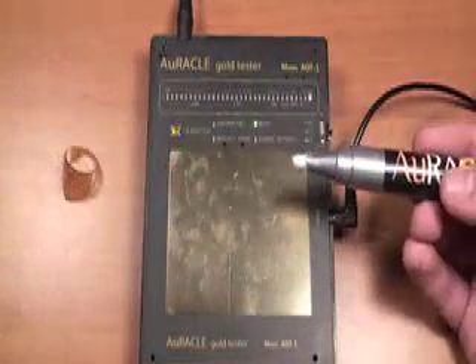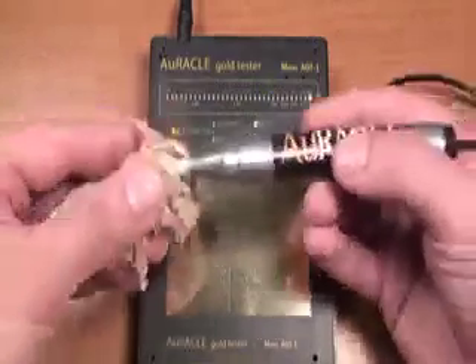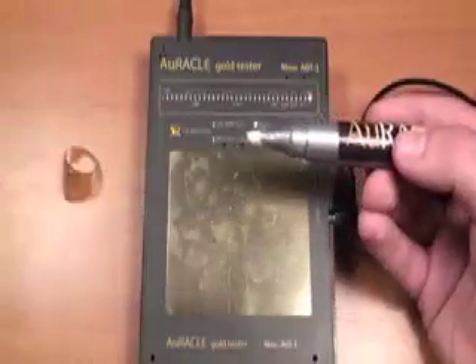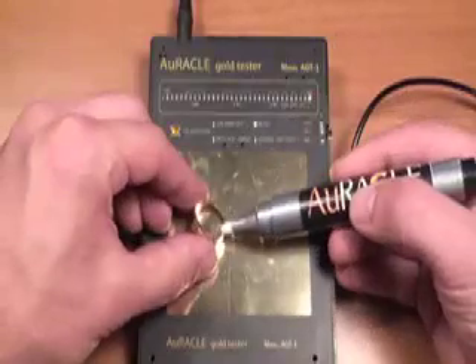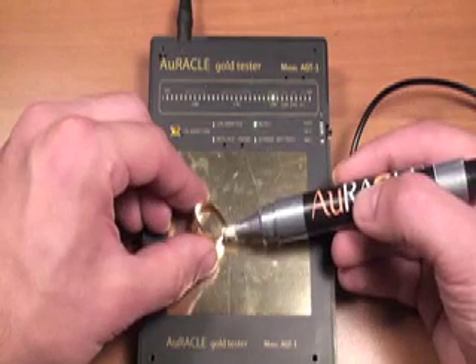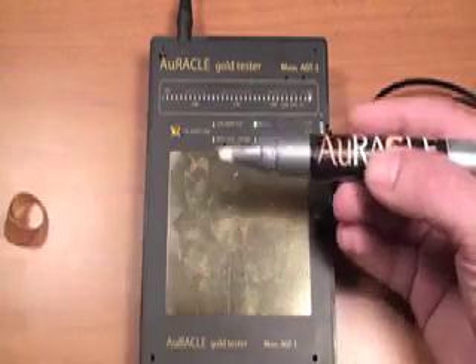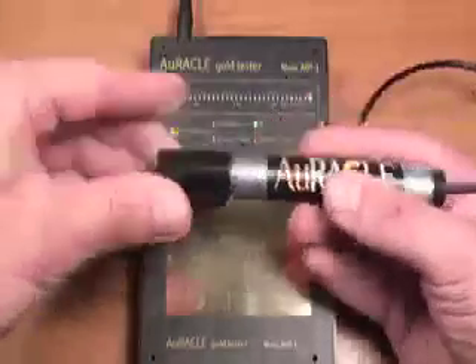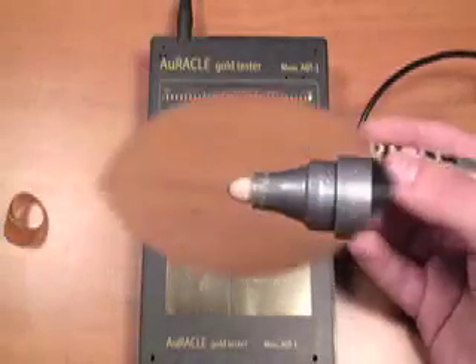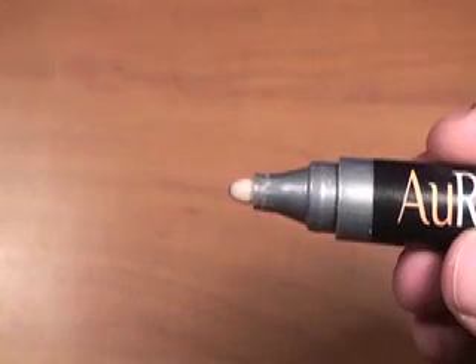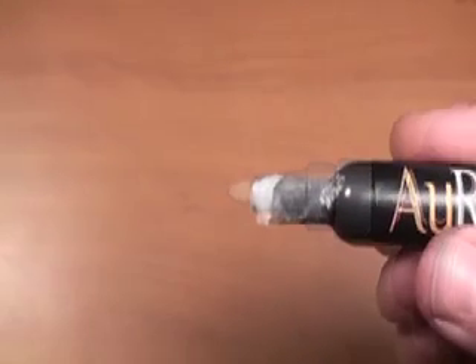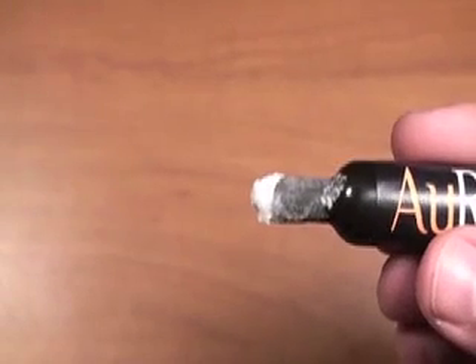As samples are tested, a residue will form on the felt tip of the pen probe. It's important to wipe the tip to remove residue that may have accumulated. It's also important to keep the gold test pad clean throughout the testing process. Keeping the cap on the pen when not in use will ensure a number of months of accurate use. Failure to do so will cause the salt solution to crystallize, rendering the pen inoperable.